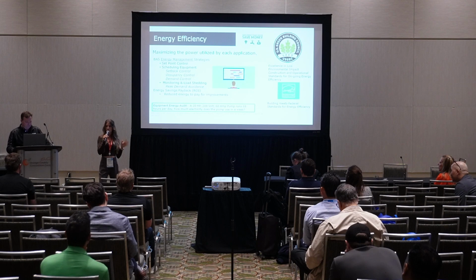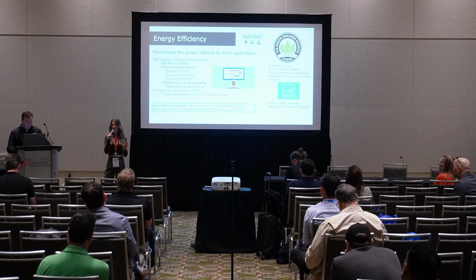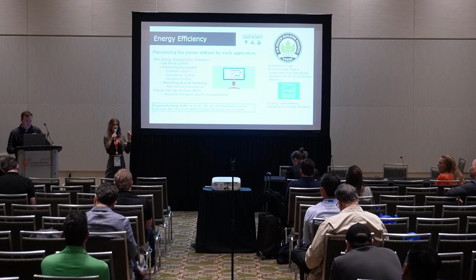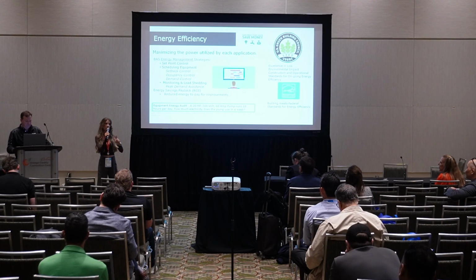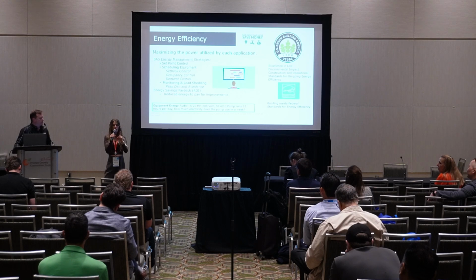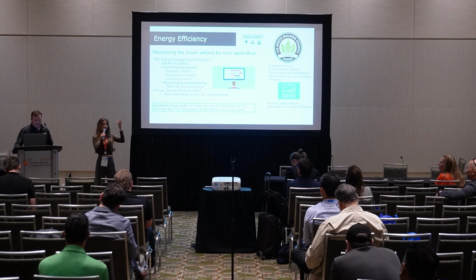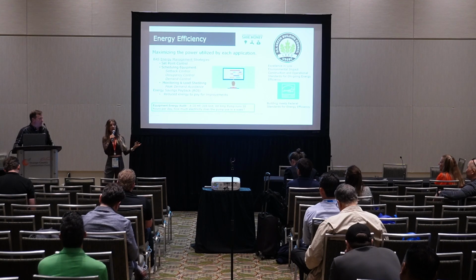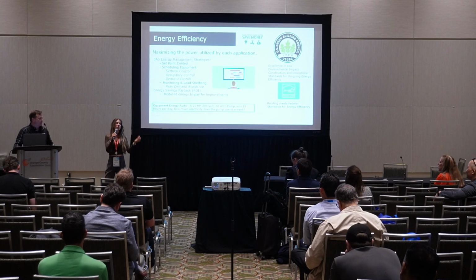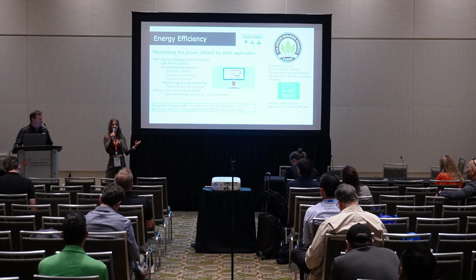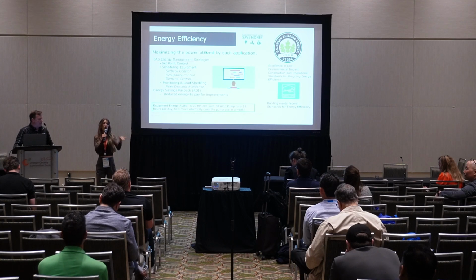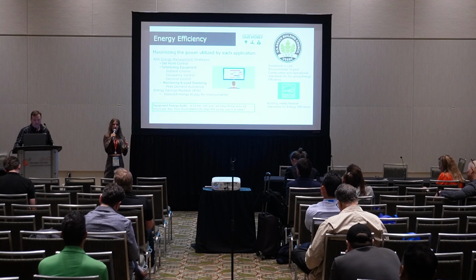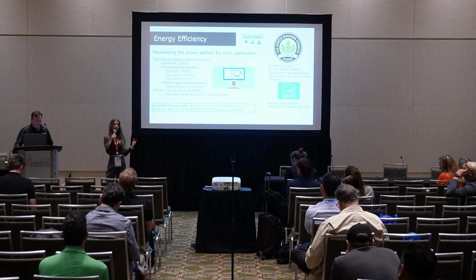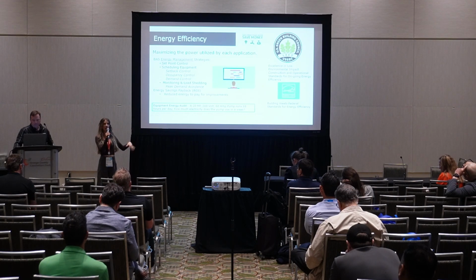We're doing a school district with 41 buildings, and I've seen this in almost every one. The nighttime setback is controlled so that as soon as one room out of a hundred drops below set point, the whole system turns on. So I say, maybe let's wait for more than one room, or do an average, it doesn't need to be that aggressive, especially when nobody's in there. The program looks fine, but if you actually look at the trends, it's on all the time. So I tell them, never trust the schedules, never trust the pictures, always look at the trends to see what's actually happening, because that's where you'll find issues. There are lots of standard ones everyone looks for, but also lots of weird ones.